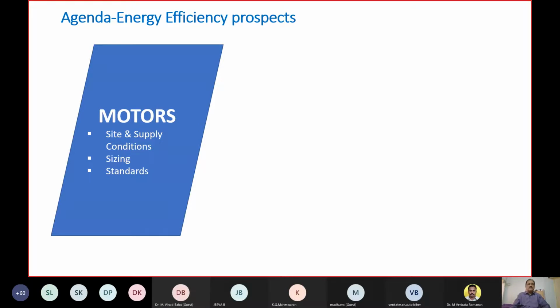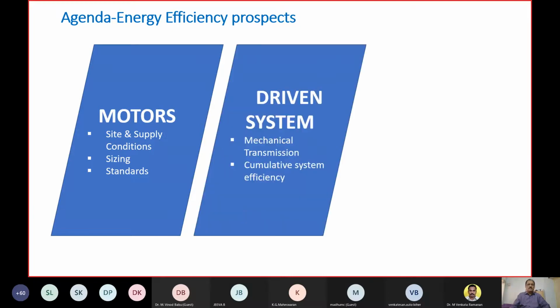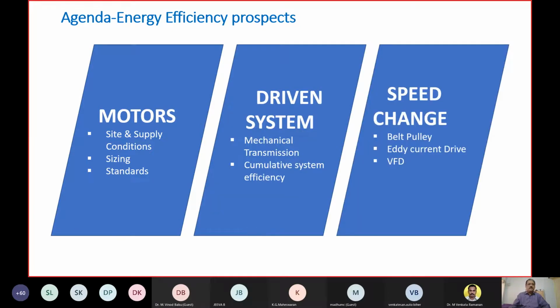So the agenda for energy efficiency prospects through motors or motor systems will be like this. For motors, the influence will be on site and supply conditions, sizing of the motors, and standards to be followed for the motors. And in the case of the driven system, mechanical transmissions and cumulative system efficiencies will be discussed with respect to fans or pumps or any other driven equipment. And very importantly, we will include a few slides on the effect of speed change through VFD, belt pulley arrangements, or eddy current drive arrangements, in order to position how many energy efficiency opportunities are available from these three focus points.